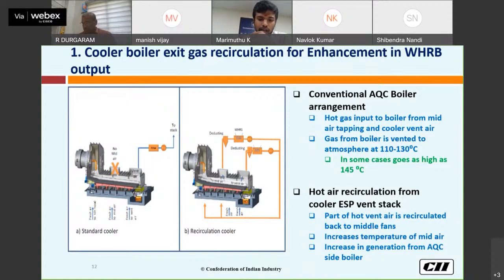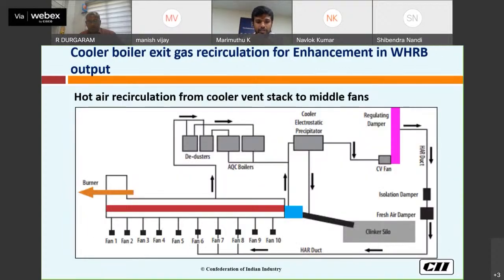So instead of giving ambient air, if we give hot air, what will happen? It will increase the heat input to the WHRB. This will help in power generation, meaning it will help in increasing the generation. This is the simplest diagram of the hot air recirculation arrangement, which is done in JK Lakshmi Cement. From the cooler mid-air, we have first a de-duster, and there is an AQC boiler. After that, we have an electrostatic precipitator. Whatever dust fine is collected in the ESP moves to the clinker silo. Then the gas goes to the stack. From the stack, the gas, which might be at a temperature of 100 degrees centigrade, is recirculated to the middle fans, fans 6, 7, 8, where the tapping for the AQC boiler is taken.